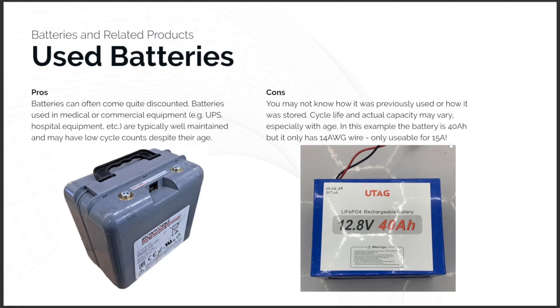The downside is you've got to really know your supplier or know what you're looking at. I found this one on eBay—good, cheap price, but in this case, same amp hour rating, same voltage, but it came pre-wired with only 14 gauge wire, so it's only usable for 15 amps. Whereas the other one, with big M10 terminals, you can do 20 plus amps out of it.